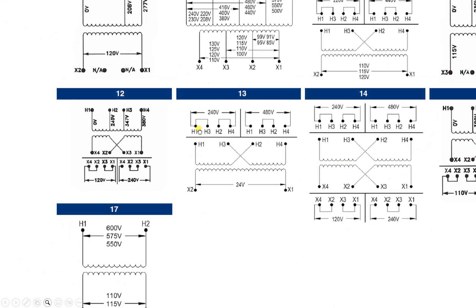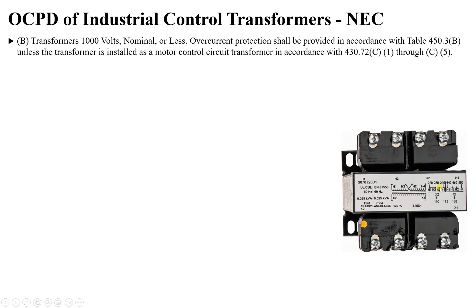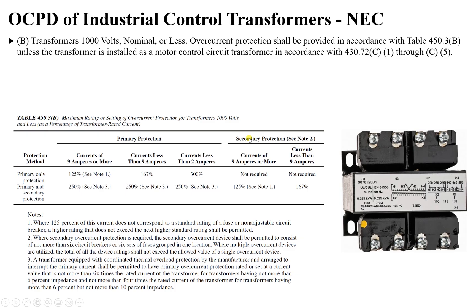For the NEC standard, there is a special case for selecting overcurrent protection devices for this type of transformer. The transformer is 1000 volts or less on both primary and secondary, so it follows NEC Table 450.3(B). This table covers transformers under 1000V and specifies the percentage rating for overcurrent protection depending on the primary and secondary current, and whether you need primary-only or primary-and-secondary protection.